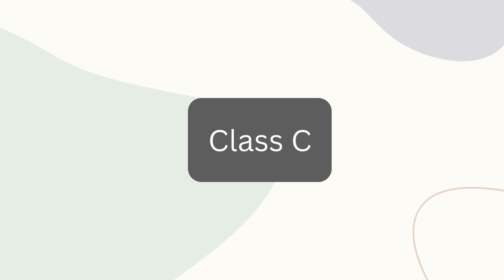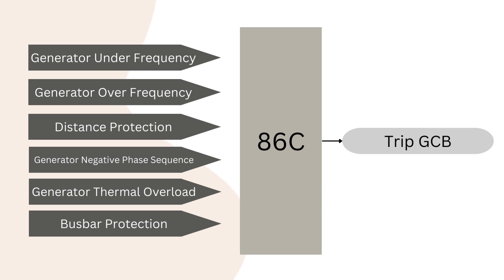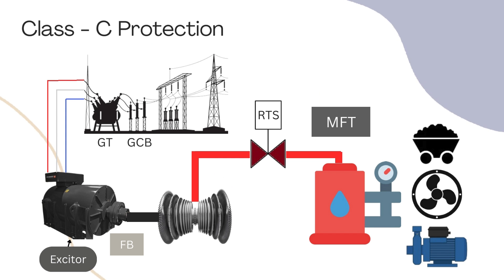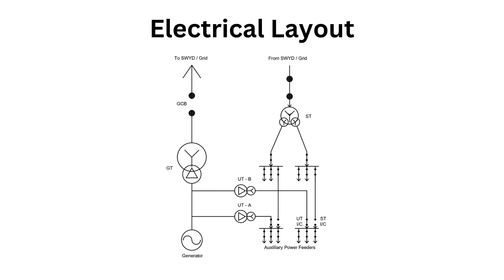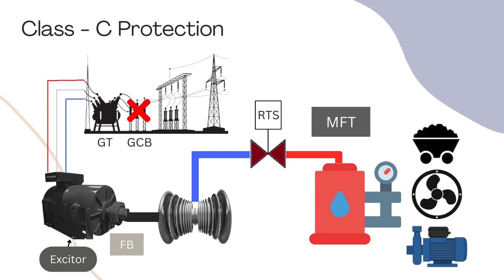Finally, we will understand how Class C protection works. In this scheme, all grid-related faults are targeted: generator under- and over-frequency, distance protection, generator negative phase sequence, generator thermal overload, and busbar protection. The trip command goes to the GCB only. For example, if generator under-frequency protection operates, it energizes the 86C relay and issues a trip command to the GCB — the generator is disconnected from the grid but not stopped. This power will go to the UTs for station requirements, a condition called generator islanding. Running the generator for unit loads (about 5–10% of generation capacity) is not economical, and generator over-speeding may also occur, so the turbine is also tripped.